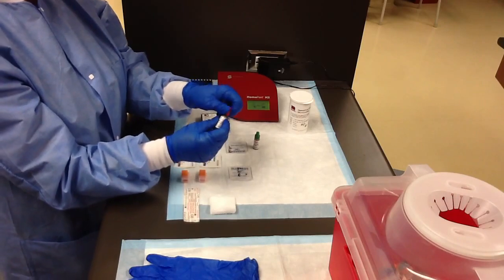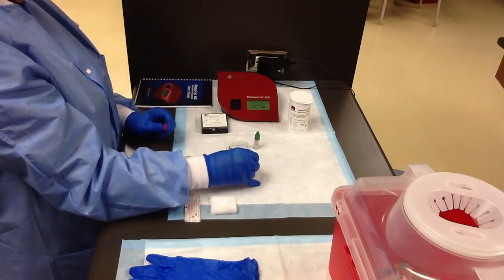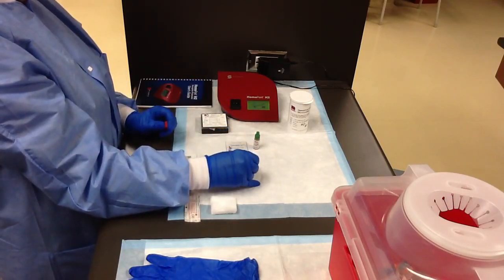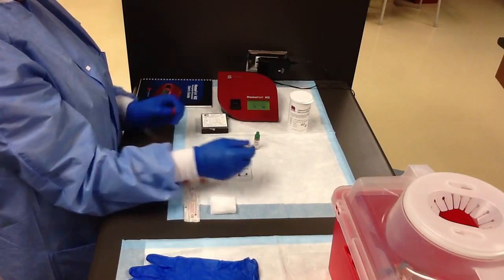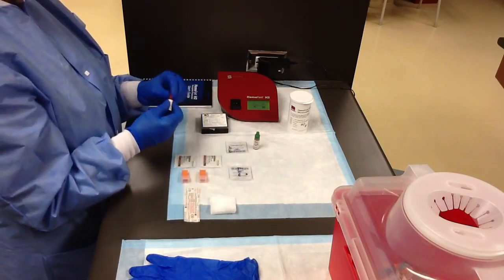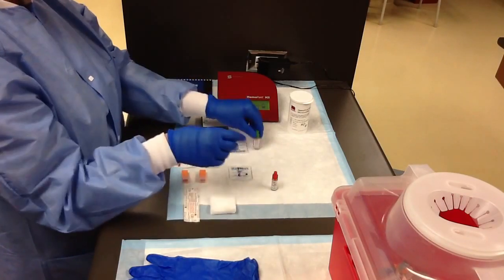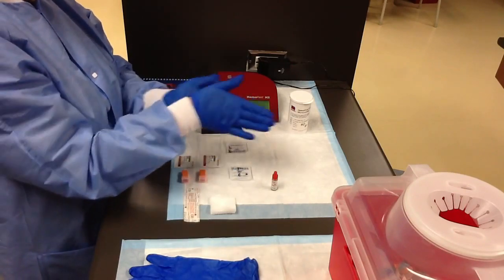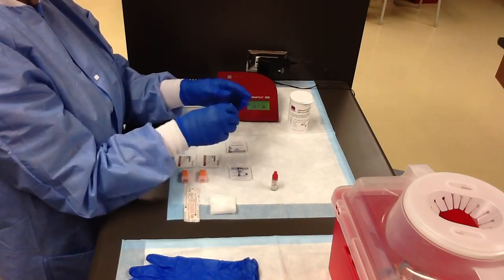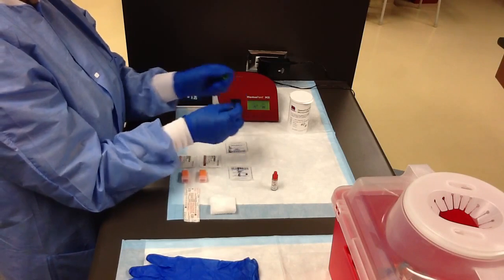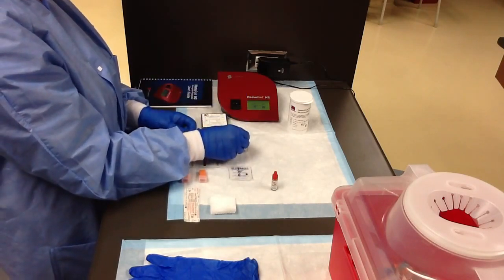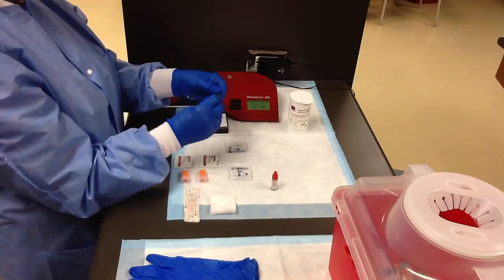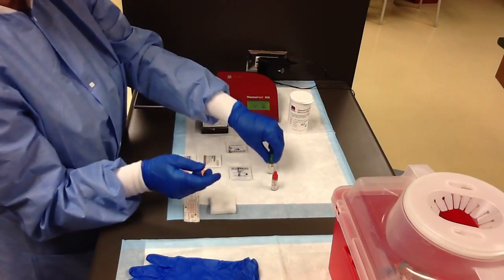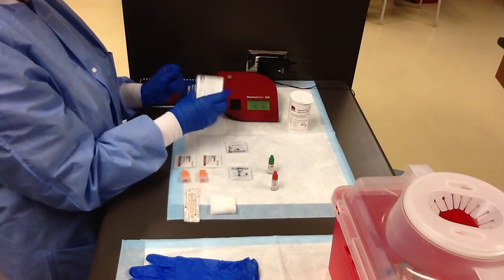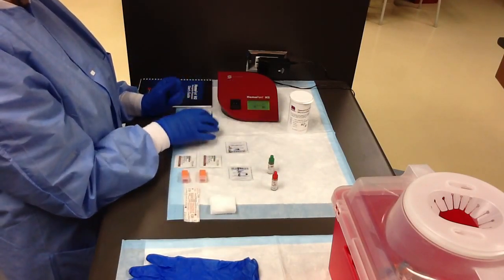You're going to take this, holding it straight up and down on the labeled parafilm. You're going to apply a drop of the low control. You're going to do the same thing for the high control. These controls can stay on the parafilm for several minutes while you run the calibration control for the machine.